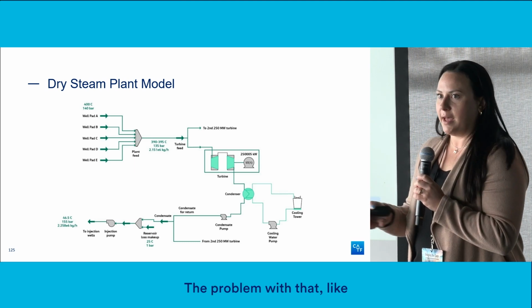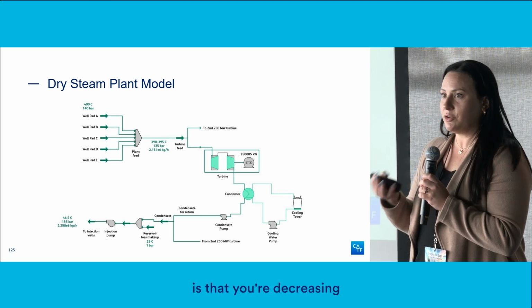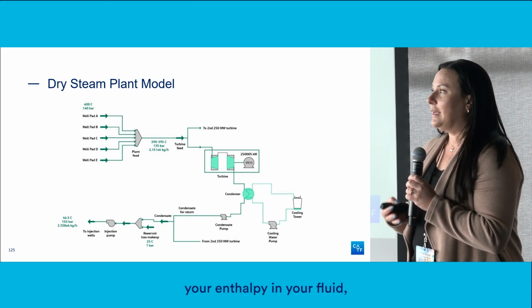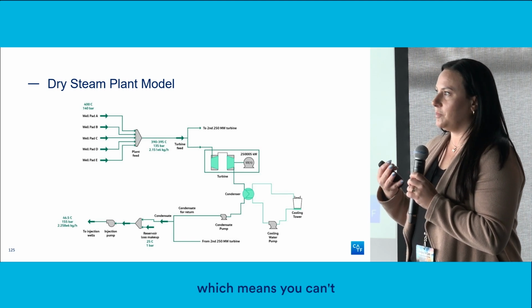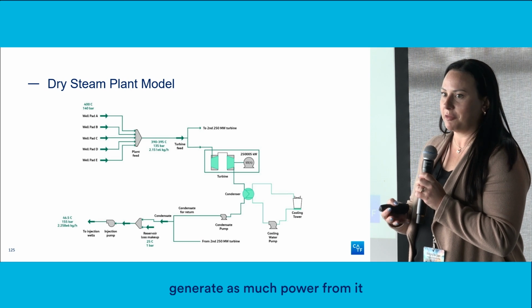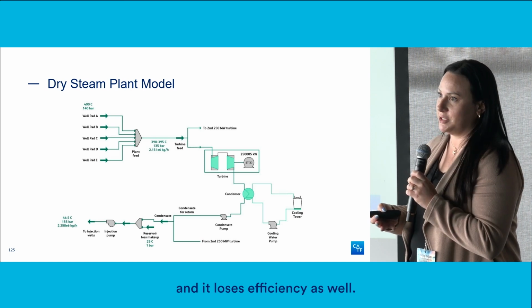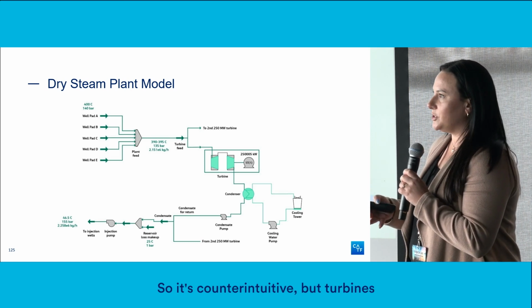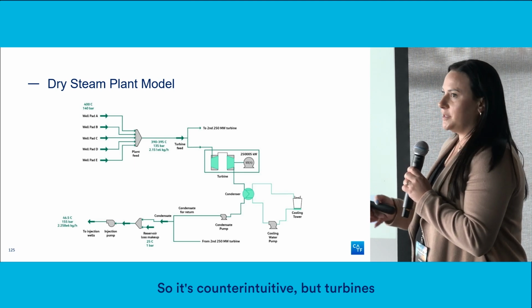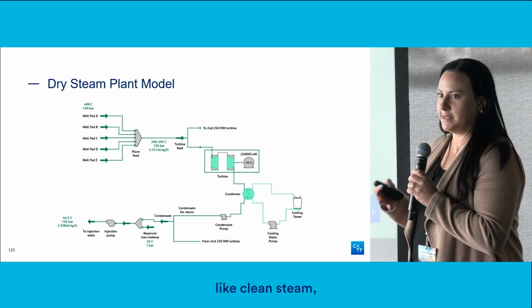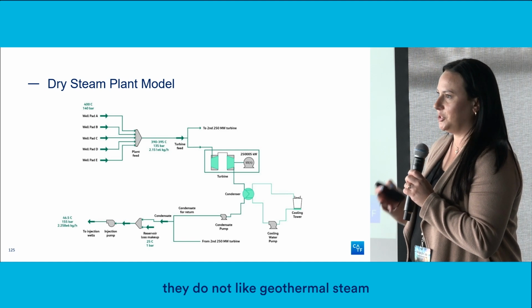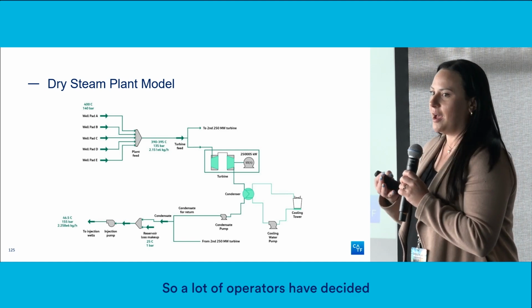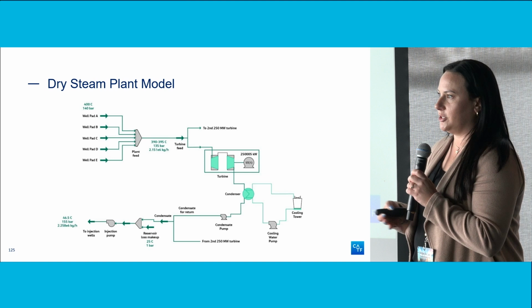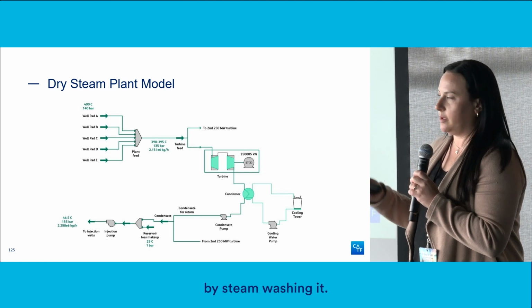The problem with that, as I mentioned, is that you're decreasing the enthalpy in your fluid, which means you can't generate as much power from it, and it loses efficiency as well. So it's counterintuitive, but turbines like clean steam — they do not like geothermal steam very much. So a lot of operators have decided to try and clean that steam by steam washing it.